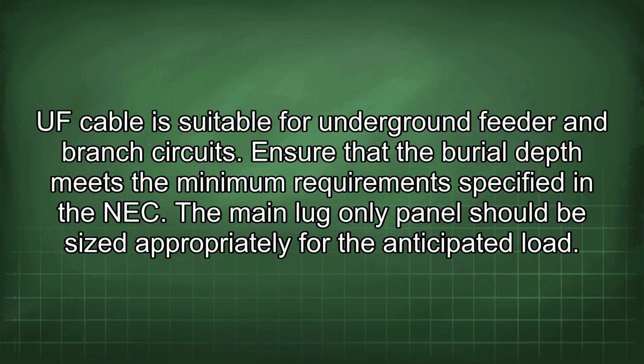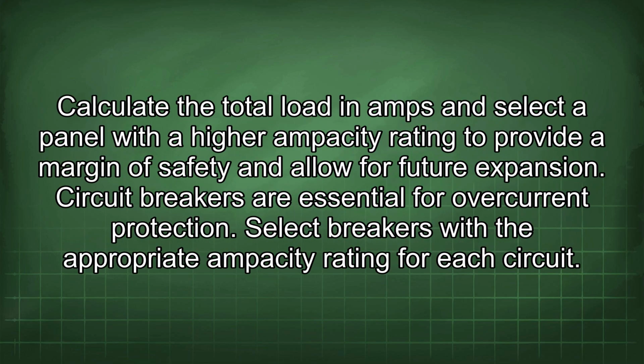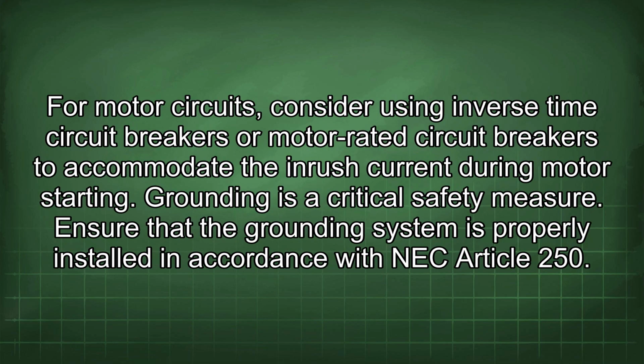The main lug-only panel should be sized appropriately for the anticipated load. Calculate the total load in amps and select a panel with a higher ampacity rating to provide a margin of safety and allow for future expansion. Circuit breakers are essential for overcurrent protection. Select breakers with the appropriate ampacity rating for each circuit. For motor circuits, consider using inverse time circuit breakers or motor-rated circuit breakers to accommodate the inrush current during motor starting. Grounding is a critical safety measure.